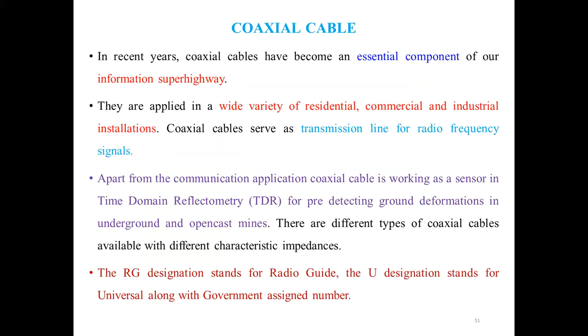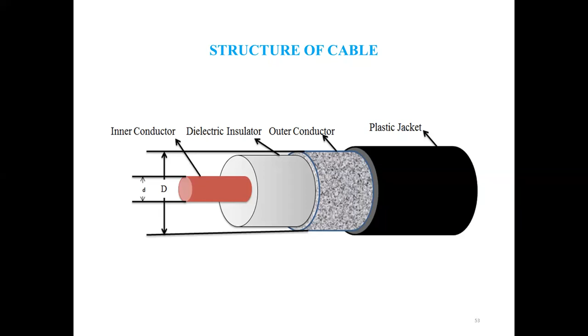As I told you, we have utilized the coaxial cable as a sensor. You can see on screen the basic structure of the coaxial cable: an inner conductor, an outer conductor, separated by insulating material. The two conductors separated by insulating material act as a capacitor, so whenever the capacitance value changes, the sensor value changes.